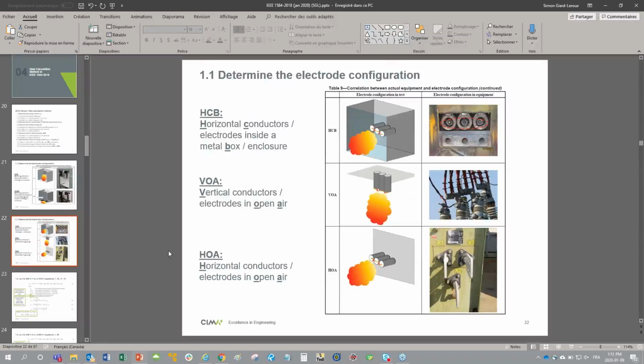For areas that I'm contracted to perform an arc flash, but I don't know the electrode configuration for the enclosure size, what would you recommend? If your equipment has fuses inside, I would recommend using HCB. If your equipment has breakers, low voltage breakers inside, I would recommend VCBB and VCB. And then if you're working on some transformer terminals or some bus bars, rectangular bus bars, for example, then I would recommend HCB because they will act as horizontal electrodes.